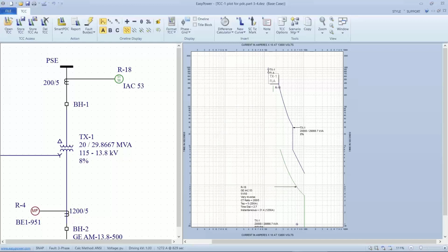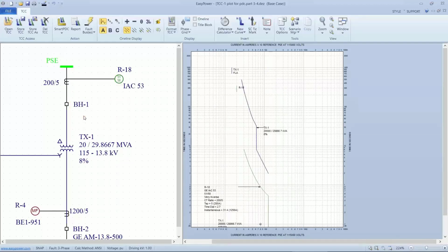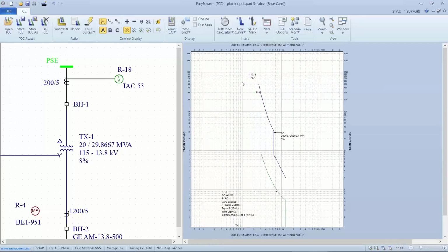Why does it display 1272 amps when we said the fault current was 150? Well, the reason is we're plotting this basis for this plot on 13.8 kV current. If we come back here and base the calculations on the TCC as the reference point, we get the same perspective, except now in the 115 kV range. And if we hover over this plot for the full load current, we see in fact it is 151 amps. Everybody see that?